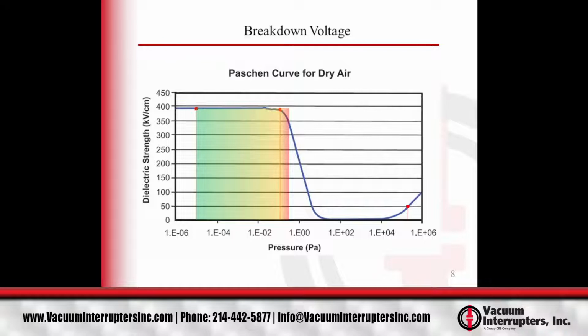So this would be the point at which vacuum interrupters would begin to fail high pot, somewhere on this falling curve. It varies for different vacuum interrupters and different internal designs. But what we want to do is replace these vacuum interrupters before they reach this point. Manufacturers of vacuum interrupters have for a long time had an upper limit of approximately 1 to the minus 2 Pascal, which is the limit at which we at Vacuum Interrupters Inc. suggest replacing the vacuum interrupter. So you're well before the point of failure, and you can prevent any type of unnecessary damage to the equipment or harm to personnel.